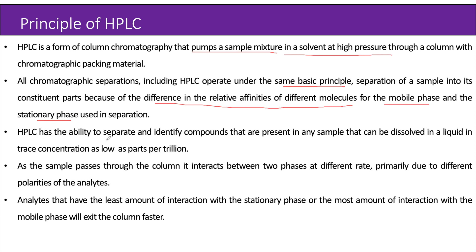HPLC has the ability to separate and identify compounds that are present in any sample that can be dissolved in a liquid, in trace concentrations as low as parts per trillion. As the sample passes through the column, it interacts between two phases at different rates, primarily due to different polarities of the analyte. Analytes that have the least amount of interaction with the stationary phase or the most amount of interaction with the mobile phase will exit the column faster.